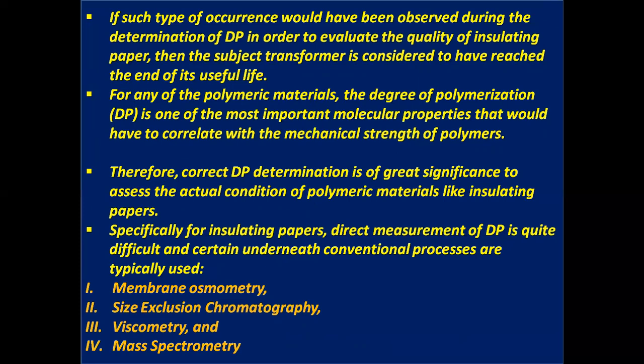For any polymeric material, the degree of polymerization is one of the most important molecular properties that correlates with the mechanical strength of polymers. Therefore, correct DP determination is of great significance to assess the actual condition of polymeric materials like insulating papers. For insulating papers, direct measurement of DP is quite difficult, and certain conventional processes are typically used: membrane osmometry, size exclusion chromatography, viscometry, and mass spectrometry.